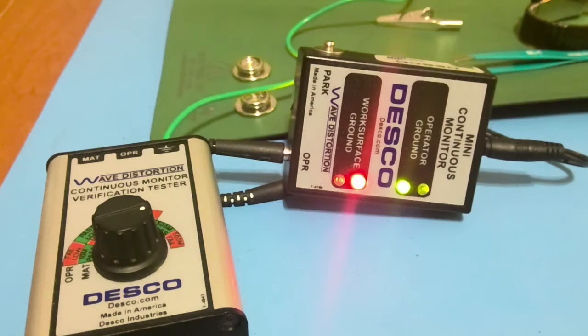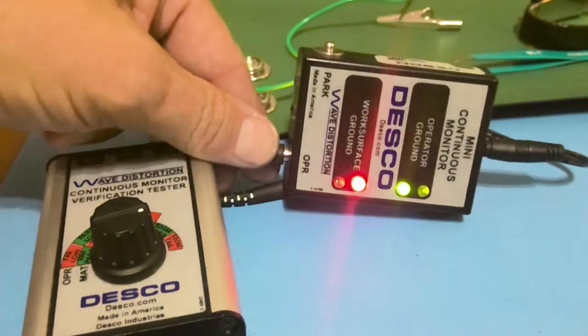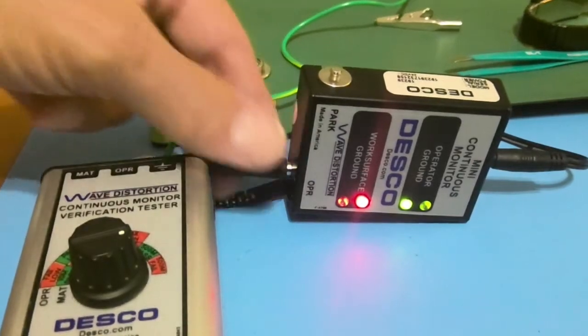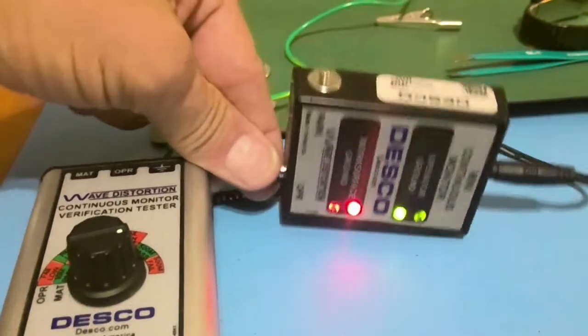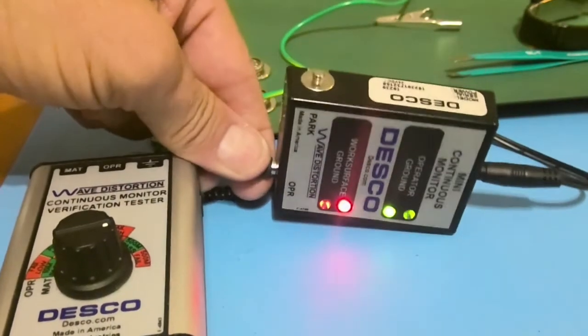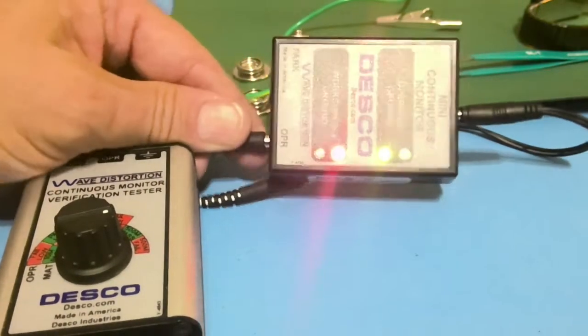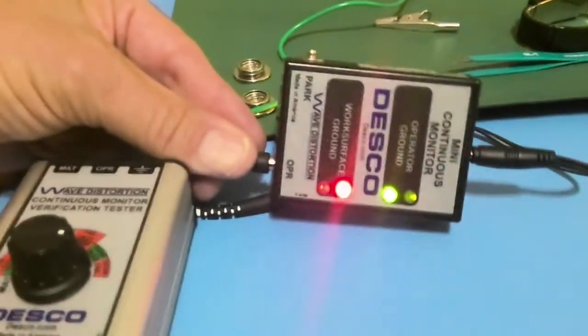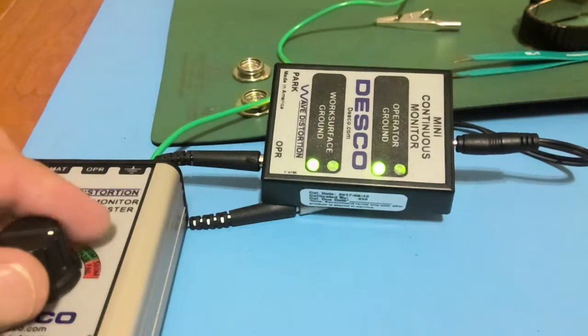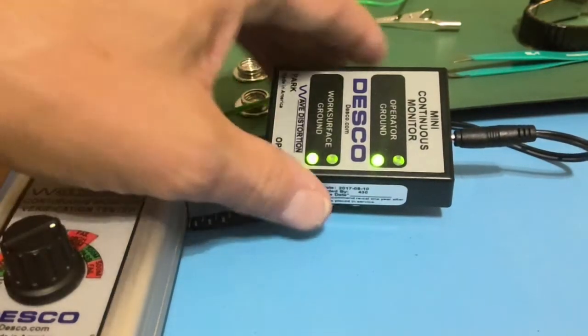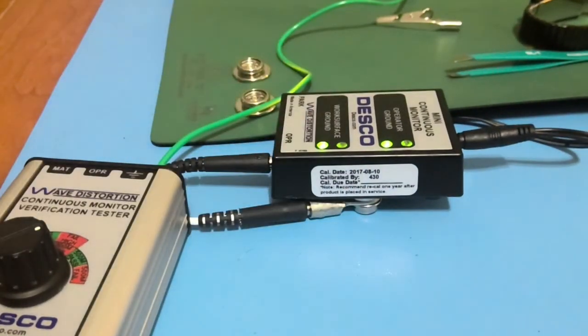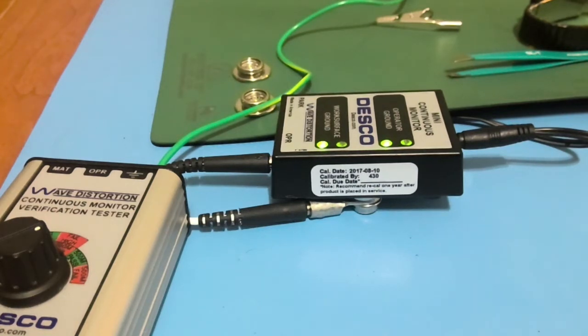You shouldn't be touching this thing nor allowing any of the snaps to touch a grounded mat. So I kind of set it up on the side. You can hold it up in the air, whatever you want to do while you're operating with it. But that is all you need to do to test. See, the snap started hitting the mat, so it got a ground, and then it will no longer beep, even though the tester is plugged in. So you have to be careful with that.